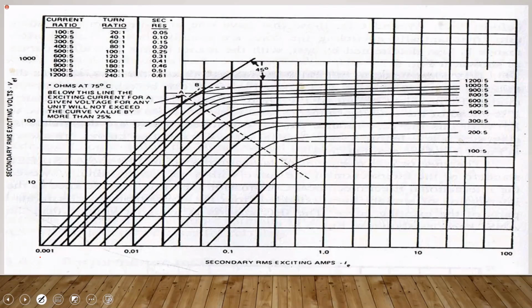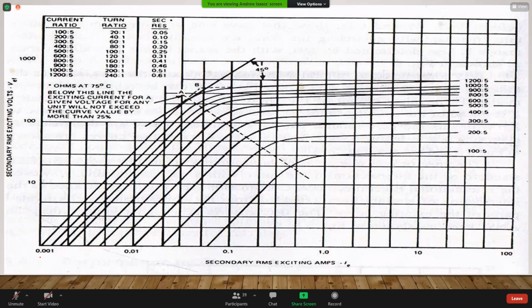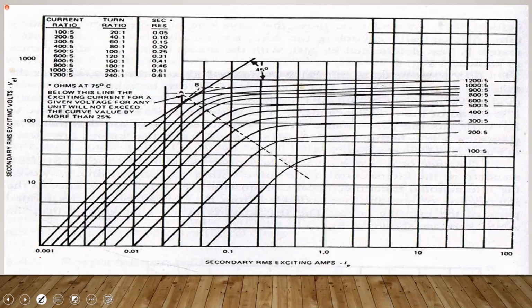With regard to the transducers, you have your CT. You know what the standard output is. For your VT, you know what the standard output is. And of course, you know that you connect your VT in parallel with the system, and your CT in series with the system. You have the figure there showing you a practical application. And of course, we have the characteristics, which give us the secondary resistance and the winding. What these things up here mean, yes, it's significant, but that's for another time.